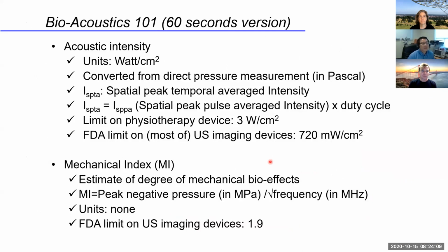I believe the earlier part of the class already covered the basic physics behind the technique, but I would like to briefly go over two main jargons that I plan to use in my lecture. The first one is acoustic intensity. Its unit is watts per centimeter square, and the value can be derived by measuring the acoustic pressure in pascals. Spatial peak temporal averaged intensity, represented as ISPTA, is the time averaged overall intensity of the ultrasound waves and considered an important indicator for potential heat deposition. Of course, the heat deposition is also related to the degree of absorption of the ultrasound by a specific tissue.